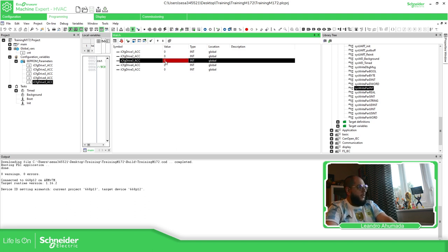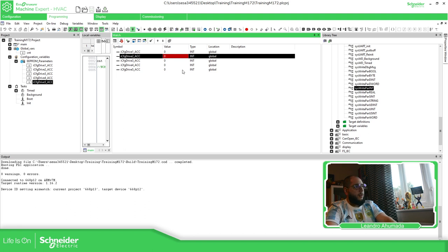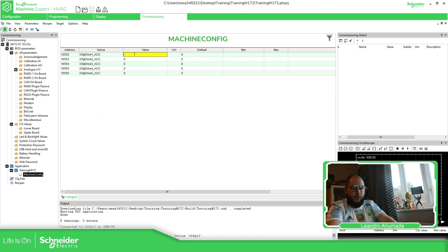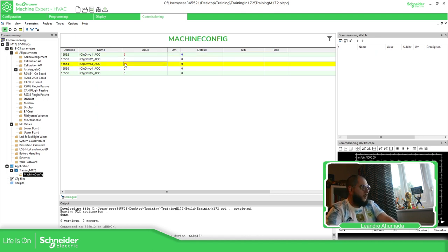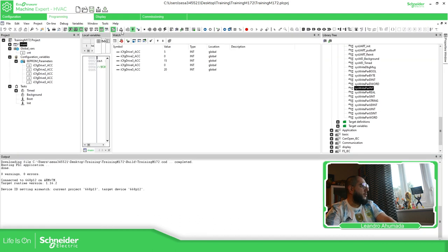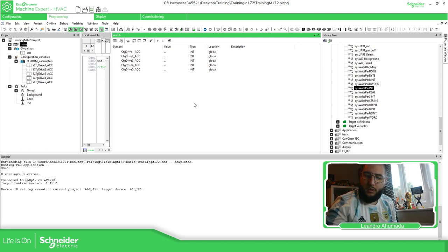The watch list doesn't allow me to modify EEPROM values directly, but from the Commissioning tab I can. I'll set a new value of 5 for the first, 15 for the second, and 20 for the third, then select all and write the new values. You can see the new values are now stored. I'm going to power cycle the equipment to confirm they persist.